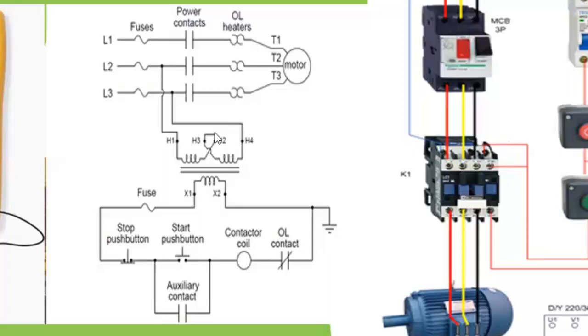Then on the control side, we also have the transformer that is feeding the control circuit. You see that we have an additional component, the fuse. We have the stop push button. We have the start push button, the retainer contact. Then we have the contactor coil, that is the coil that is operating this contact. Then we have the overload contact, which is tied to all of these overloads.